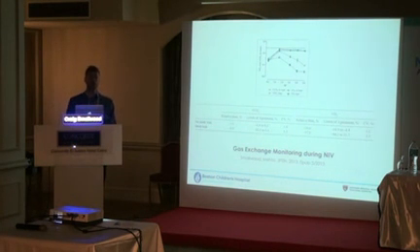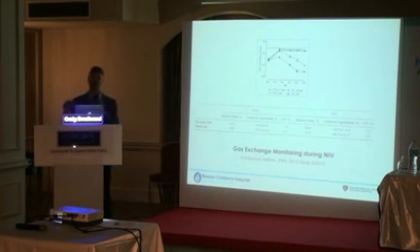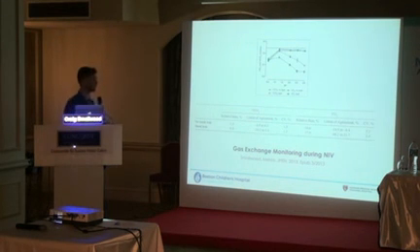So during non-invasive ventilation, we know there's tons of leaks. And so the amount of flow that's going into that patient and coming out of the ventilator is much higher than their actual minute ventilation, because the ventilator is going to be compensating for leaks in the system and around the mask or nasal interface. But we had to look at that total flow rate and match it specifically to the indirect calorimeter. And that's basically right here, 1. So the higher this dot to this dashed line was the increased accuracy. So the closer those two things met was the superior accuracy.